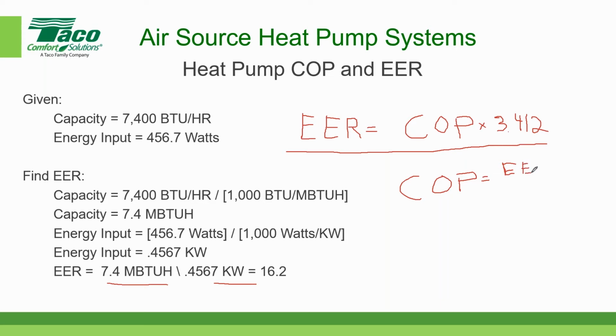divided by 3.412. So let's do the math out here. If our EER is 16.2 divided by 3.412, then our COP would be 4.7. So that's where those numbers come from. Isn't that interesting? Any questions about that? No.